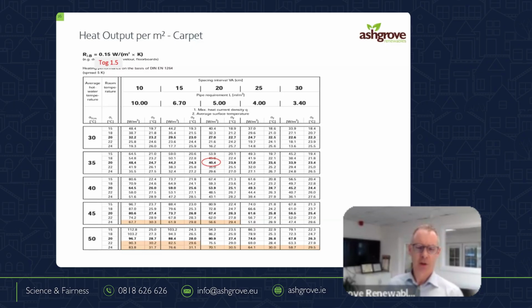But that's kind of a typical house today that doesn't have a lot of windows. But if I put the pipes in here, you can see here pipes are in the floor at 20 centimeters apart, and I'm going to get 40 watts. But importantly, I'm running my heat pump at 35 degrees. So we know from the last few charts that that's going to give us a high COP and a lower running cost, right? The next thing is if I here want to produce 100 watts.